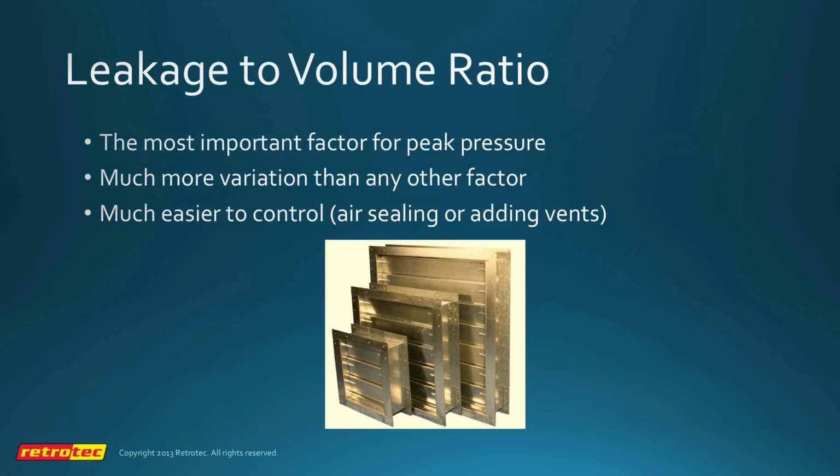Now, in some cases, people are using peak flow rates. Peak flow rates imply a leak to volume ratio, and leak to volume ratios imply a peak flow rate, because if you've got a certain volume, it's going to require a certain flow rate to get the agent up to concentration. So they don't obviously appear to be the same, but they are actually the same.